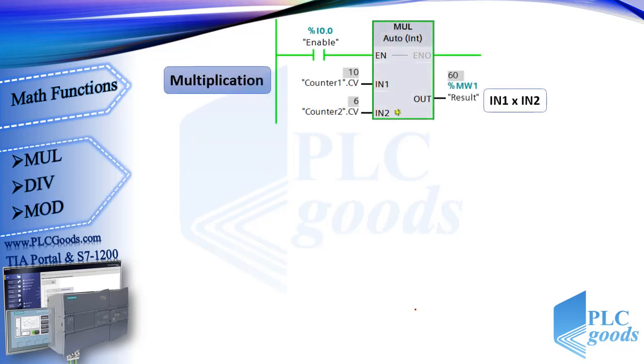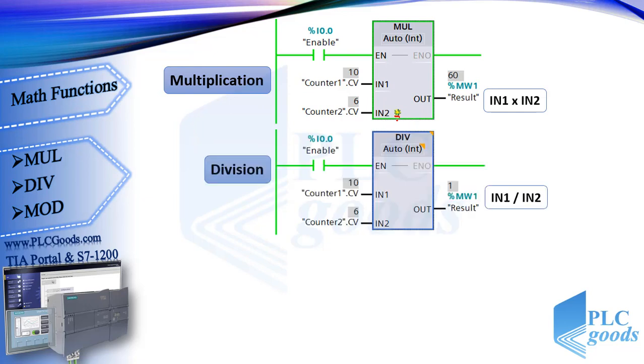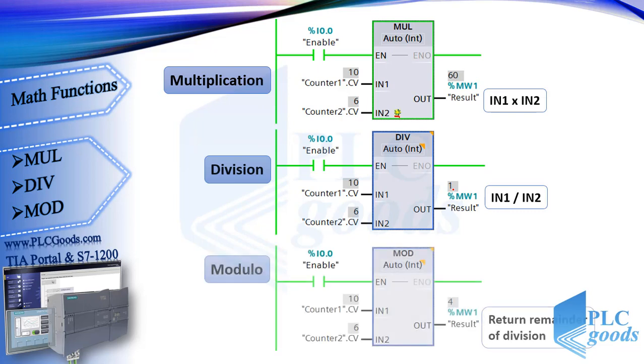Now let's see other functions in TIA software. This is the ladder symbol of the multiply instruction — this function multiplies 10 with 6 and stores 60 at MW1. As you see, this instruction can multiply more than 2 values. Next is division — this instruction divides 10 by 6 and returns its quotient. Next is MOD (modulo) — this instruction divides IN1 by IN2 and sends the remainder of the division to its output.